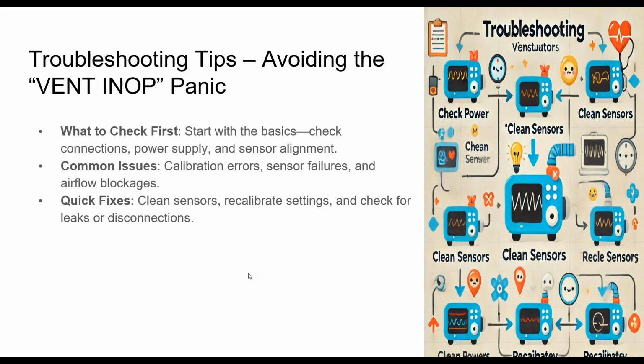So another common issue, I'll get off of calibration issues, but this is a good example that I just mentioned: sensor failures. Sensors do fail. They fail for a lot of reasons, but just to reiterate, some of those reasons are how clean the ventilator is over time and how long the ventilator has been used, period. That's why a lot of ventilator manufacturers have explicitly said to replace these components on an hourly or metered basis. They believe that over time, that component will wear because of the environment and the conditions it's put through.